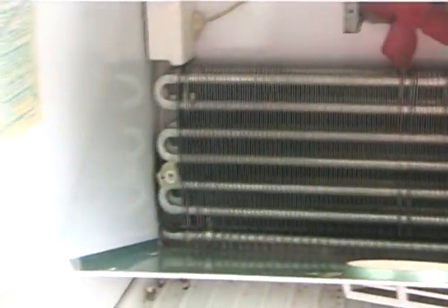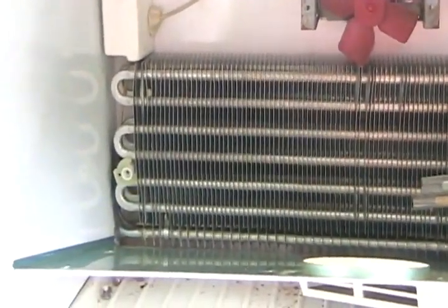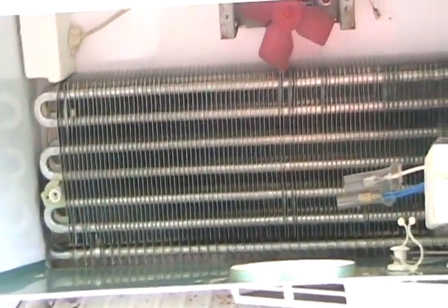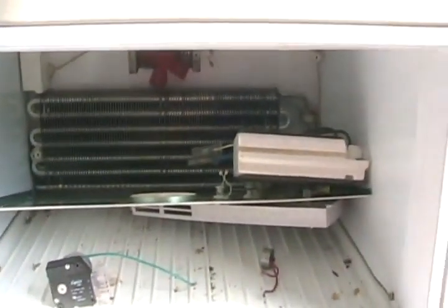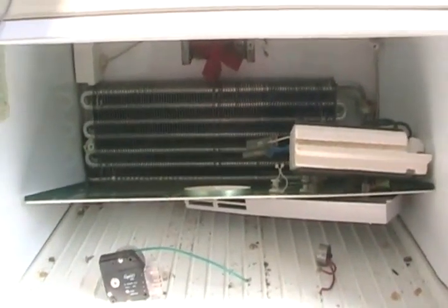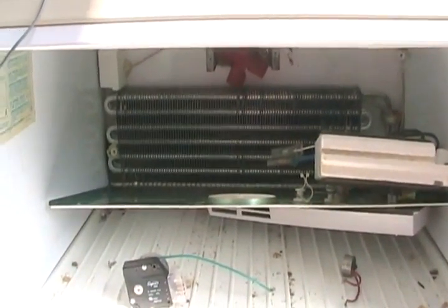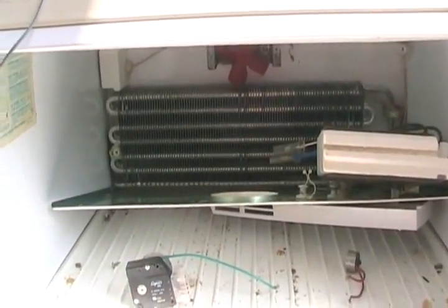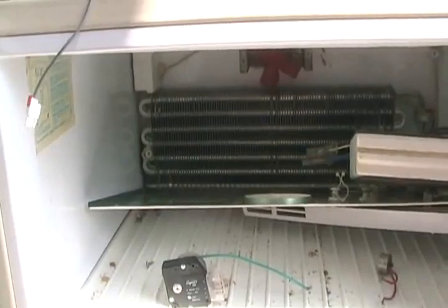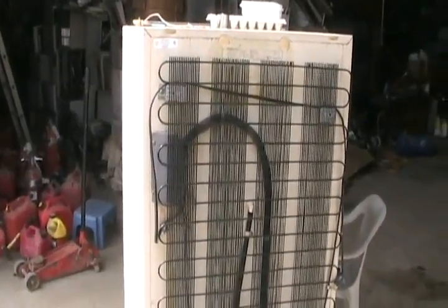The other most common place where fridges leak is the evaporator coil, since it's just made out of thin aluminum. The thing it doesn't like most — which even eats copper — is tomatoes. People who do a lot of tomato freezing or processing, or use their freezer or fridge to store tomato paste, tomato sauce, or juice, find their fridges don't last as long, because it creates an acid that eats through the coils.